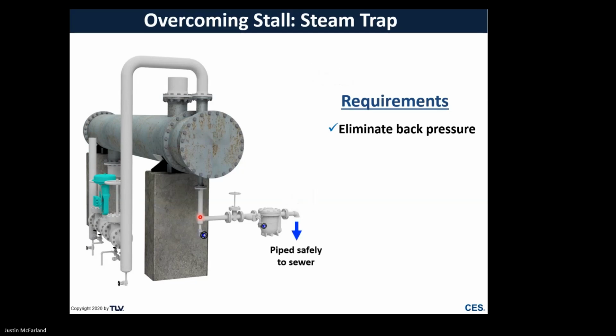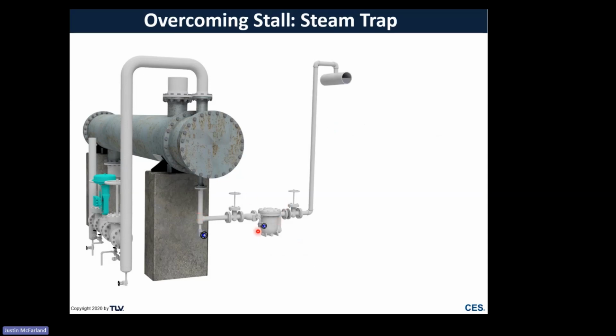Yeah, thanks. And upstream of the trap, it's all the same pressure, right? So it has to flow to the trap through gravity, regardless of what's happening downstream. So you can't put the trap above the minimum water level of the heat exchanger, or you're creating a stall condition, right? Great point, you absolutely want to have the trap below the outlet of the heater so you can gravity drain from the heater through the trap. If it's above that, well then the pressure in the piping here is going to be the same as the pressure in your heater, and it's like a manometer. It would literally have to back up condensate in the heater in order to be able to drain through the trap. Now, this scenario is also assuming that you've got positive pressure inside the heater. A lot of times you might not have positive pressure, so lifting up the trap wouldn't help at all.